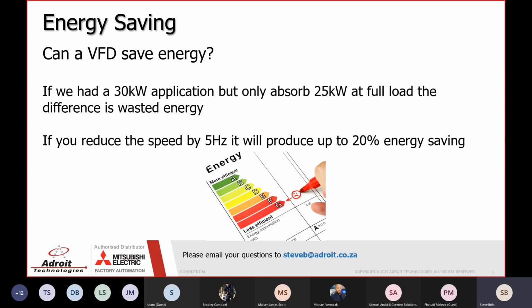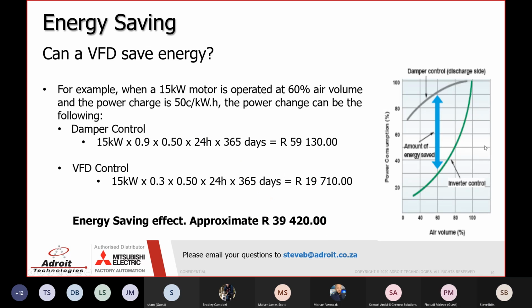So can a VFD save energy? Absolutely. If we had a 30 kilowatt application but only absorb 25 kilowatt at full load, the difference is wasted energy. Now, in a lot of applications, you only need to reduce the speed by 5 Hertz to get up to a 20% energy saving. For example, when a 15 kilowatt motor is operated at 60% air volume and the power charge is 50 cents per kilowatt hour used, the power charge can be the following.